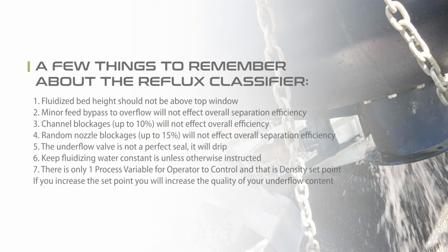Things to remember about the reflux classifier. The fluidized bed height should not be above the top window. Minor feed bypass to overflow will not affect overall separation efficiency. Channel blockages up to 10% will not affect overall efficiency. Random nozzle blockages up to 15% will not affect overall separation efficiency. The underflow valve is not a perfect seal. It will drip. Keep fluidizing water constant unless otherwise instructed. There is only one process variable for the operator to control, and that is density set point. If you increase the set point, you will increase the quality of your underflow content.